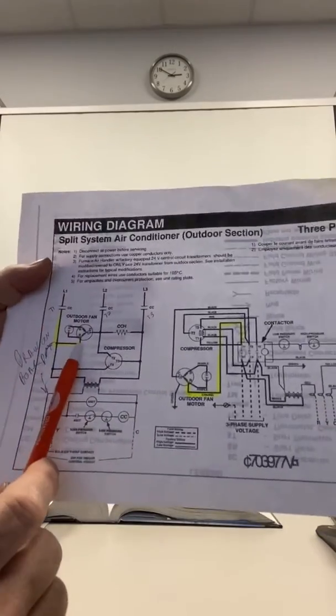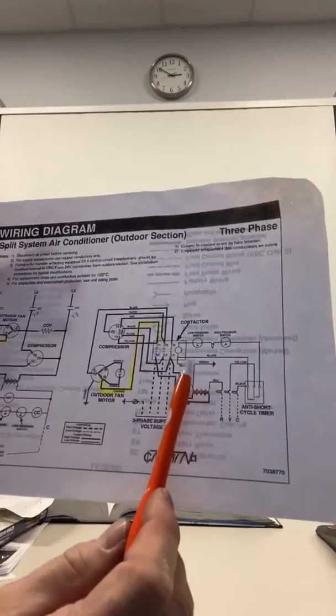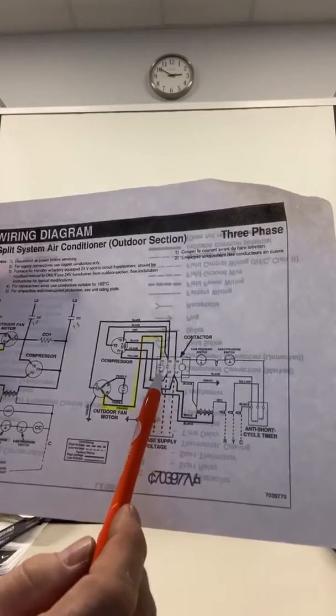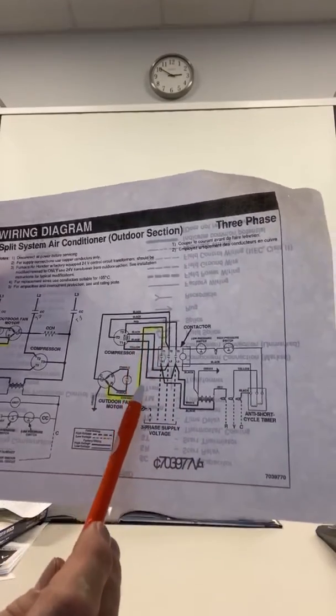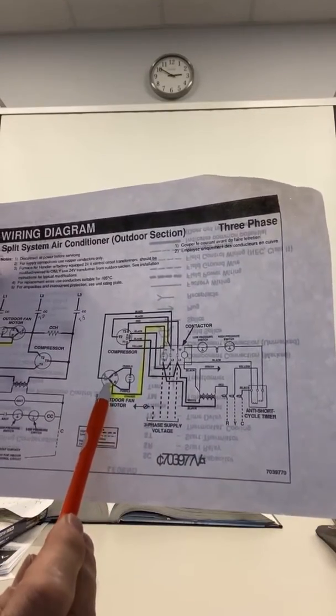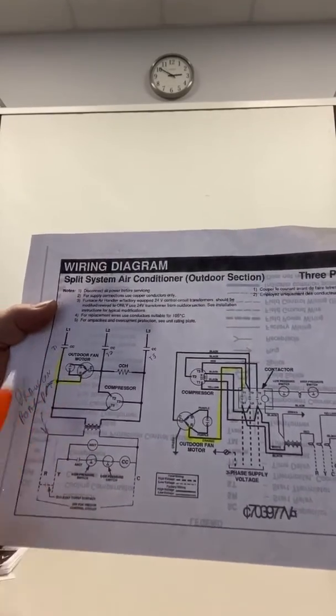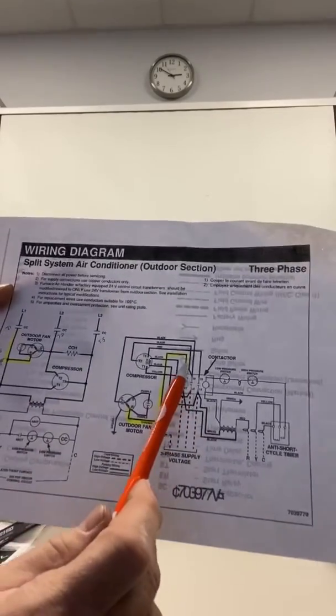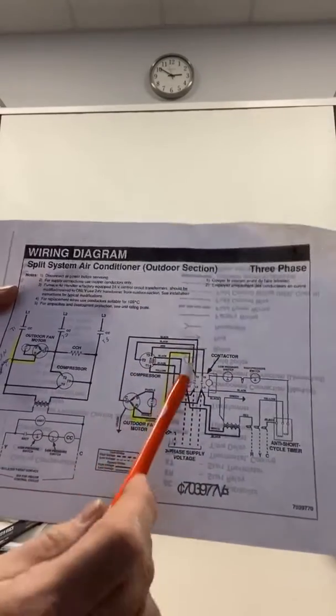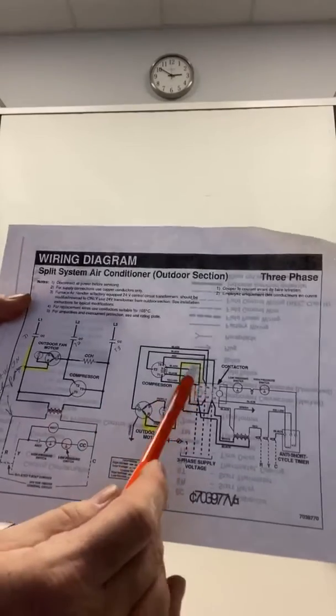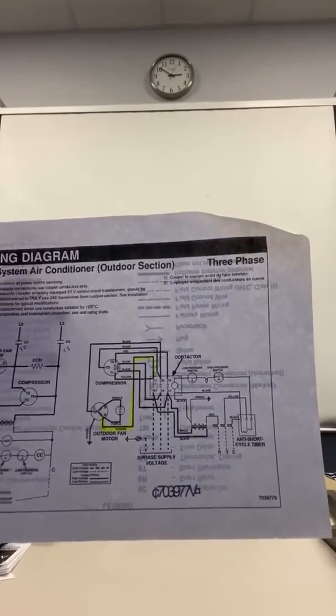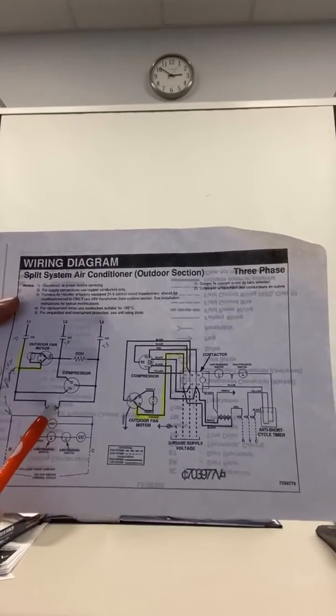But let's find that same circuit over here. Well, I'd have to find L1 on my contactor, follow it all the way back to run, and it goes to my fan motor. But you can see how quickly right here I saw run went right to L1. But notice when you're doing pictorials, they can be quite confusing because you could even cross a wire and end up in the wrong place. I do like pictorials, but they're not as fast as I can survey or come up with a synopsis with a line diagram. That's really fast.